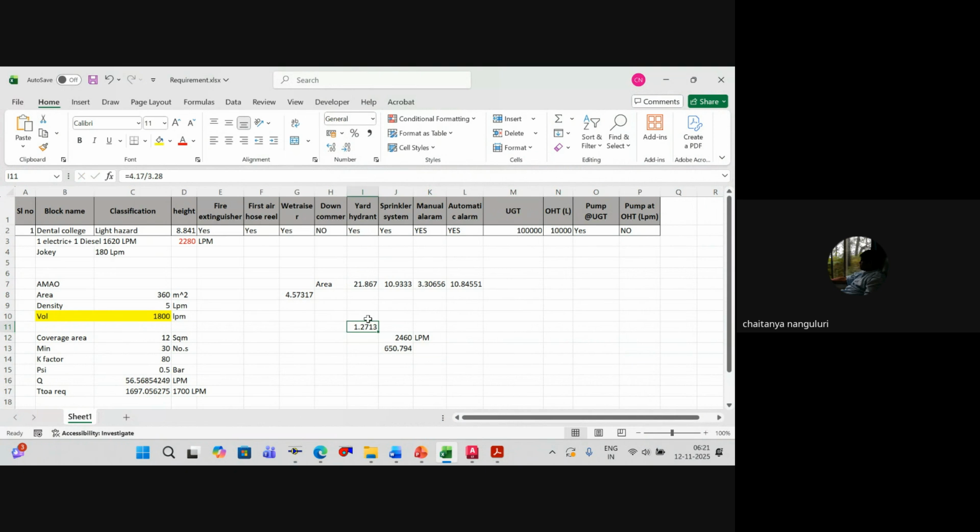Two conditions. Generally on the suction side, you design it with around 4 feet per second. I am generally comfortable with FPS, because I came from the HVAC background. But anyway, around 1.2 or 1.3 m/s you can take it.